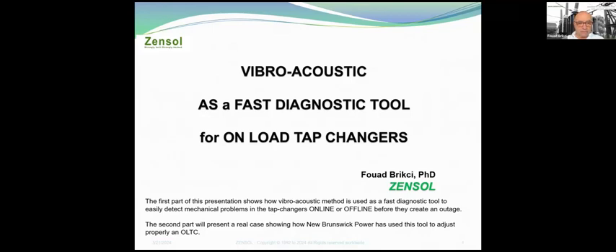The first part of this presentation shows how the vibroacoustic method is used as a fast diagnostic tool to easily detect mechanical problems in the tap changers, online or offline, before they create an outage. The second part will present a real case showing how New Brunswick Power has used this tool to adjust an OLTC properly.